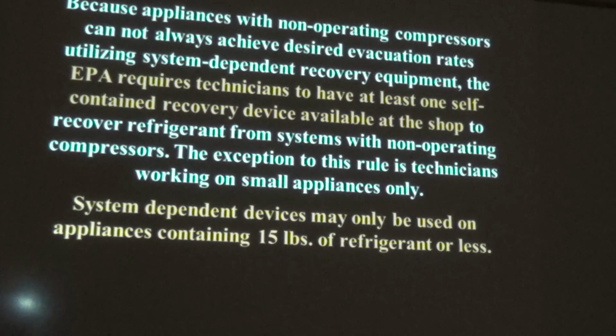Because appliances with non-operating compressors cannot always achieve the desired evacuation rates using system-dependent recovery equipment, the EPA requires the tech to have at least one self-contained recovery device, in other words, a recovery machine with its own compressor, available at the shop to recover refrigerant from systems with non-operating compressors. And if you have more than 15 pounds of refrigerant, you're going to be following another set of rules.